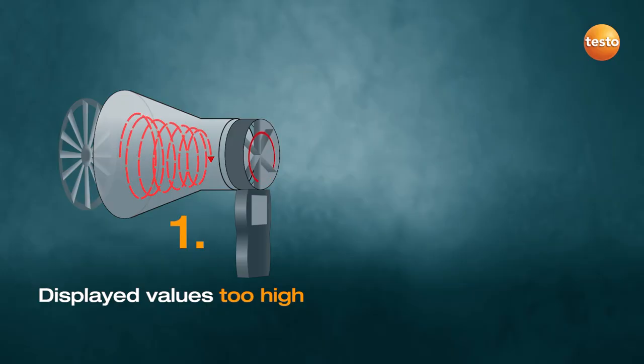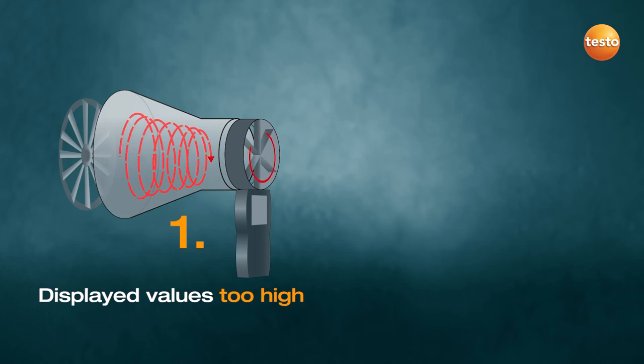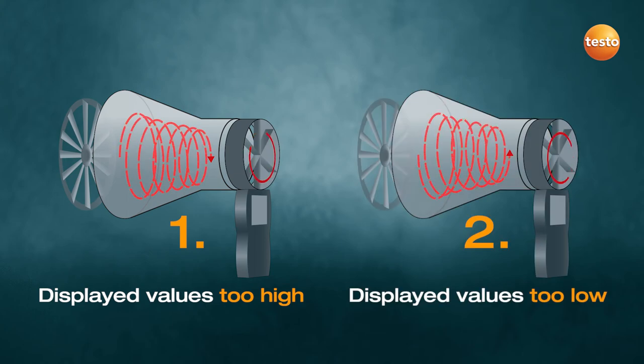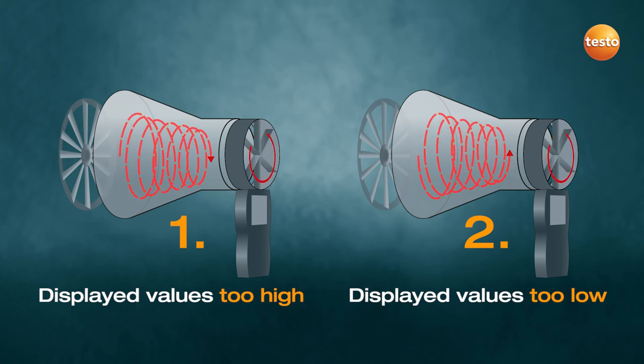Let's take a closer look at what happens. First, if the direction the swirl rotates is the same as that of the vane, the flow hits a larger cross-sectional area of the individual blades, making it accelerate too fast. Second, if the direction the swirl rotates is opposite to that of the vane, the flow passes between the individual blades and doesn't accelerate properly — resulting in an inadequate flow velocity being displayed.